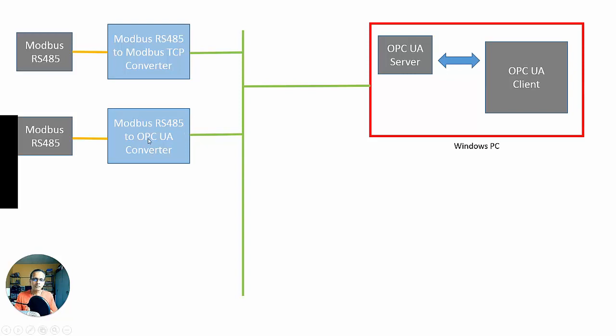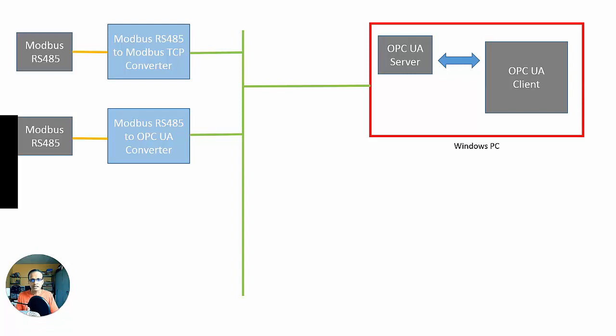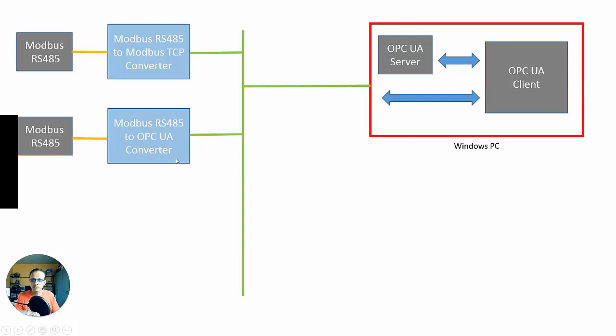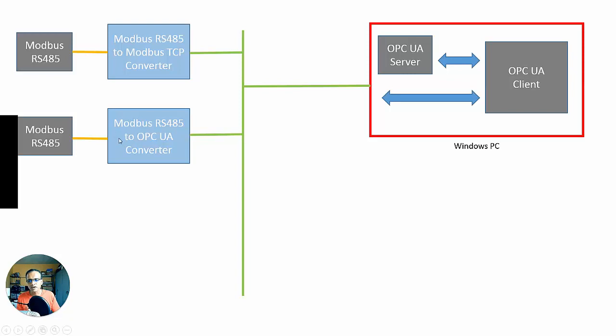Because you could implement OPC UA server on an embedded device now, like just a device that clicks onto a DIN rail and connects to the Ethernet network. So, you could have this one, there'll be an OPC UA server in here, so that now the client could communicate on the network to the OPC UA server. So, the OPC UA server, in this case, is not on Windows, it's on some sort of embedded device. But there's still sort of protocol conversion going on here. Modbus 485 to OPC UA.